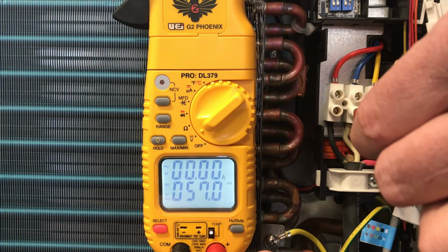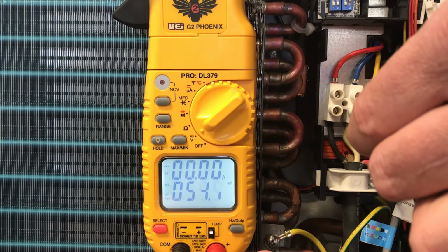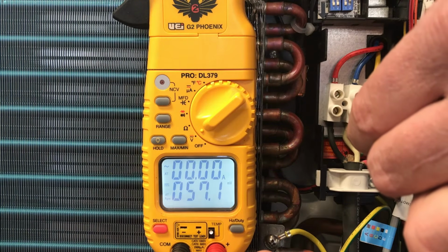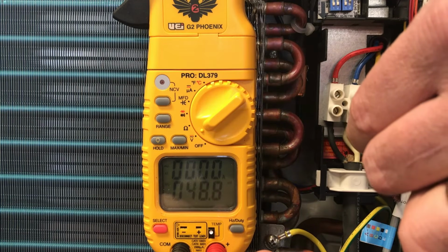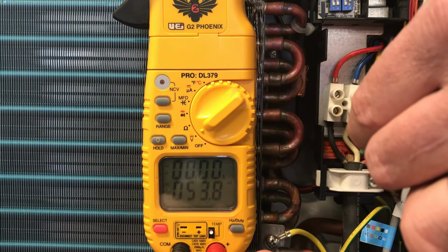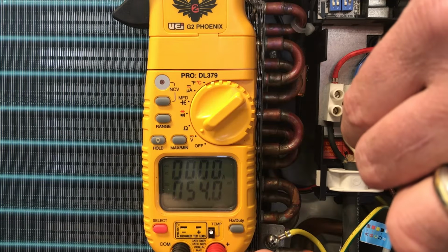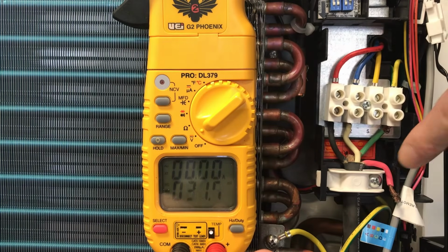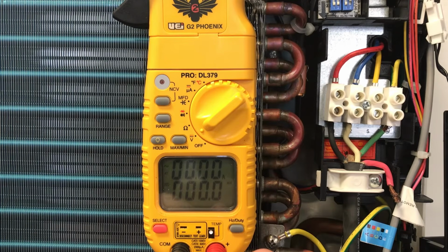Now you see we have a positive DC voltage fluctuating, kind of like we had when we thought we had an issue outside. So what we have done here, if you look, we've disconnected the S wire going to the outdoor unit. So what this is telling you is that we're getting a good DC signal out of the outdoor board because we isolated it, and our problem isn't with a circuit board. The problem is with our wire from the inside to the outside.